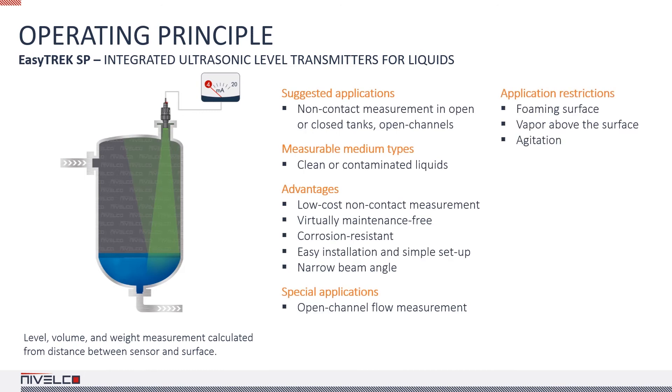The EasyTREK is an integrated device similar to the EchoTREK transmitters in many respects. The most significant difference is that the EasyTREK cannot be equipped with a plug-in display — it can only be programmed remotely via eView or a Multicont process controller through HART. The EasyTREK SP300 integrated transmitters for liquids with IP68 protection are designed to endure even occasional immersion. However, prolonged immersion must be avoided as it interferes with measurement and can cause loss of level signal even after the level returns within the measuring range.